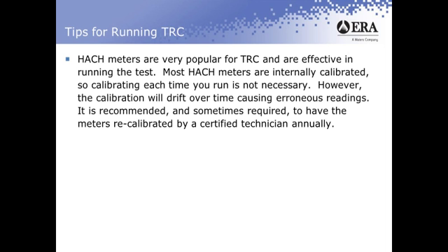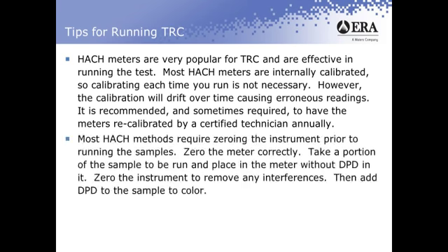So I would recommend, and I know some states do actually require this, having those meters recalibrated by a certified technician annually. And if you want to correlate this with your DMR QA study, I think that would be a very good idea.